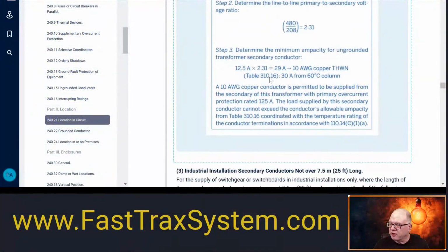So in this case, determine the minimum. Determining the minimum ampacity for ungrounded transformer secondaries would be the 12.5 times 2.31, which is the ratio right here. That would be a 10 for 29 amps. If you go to Table 310.16, 30 amps from the 60-degree column is a 10.